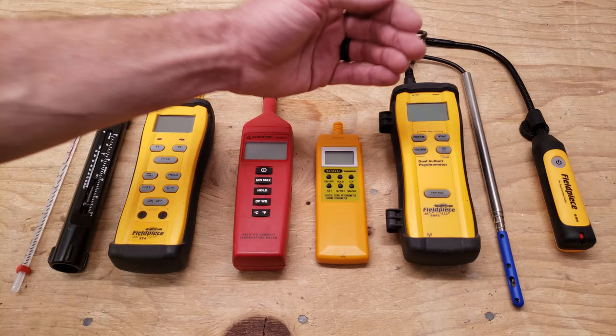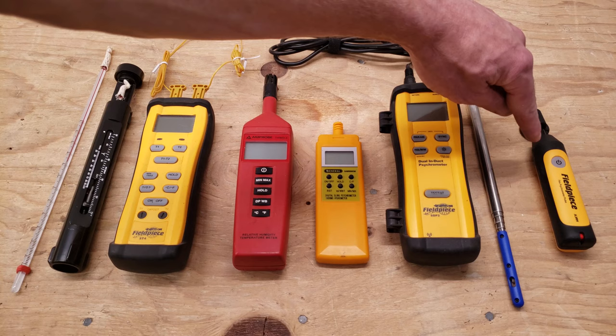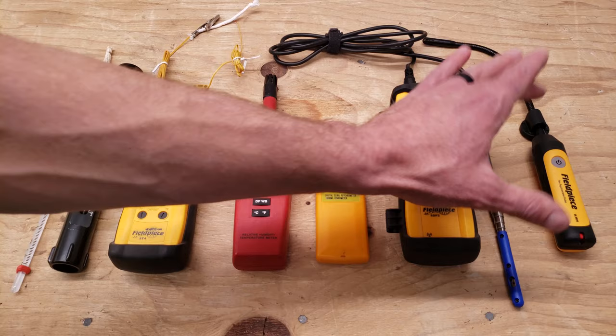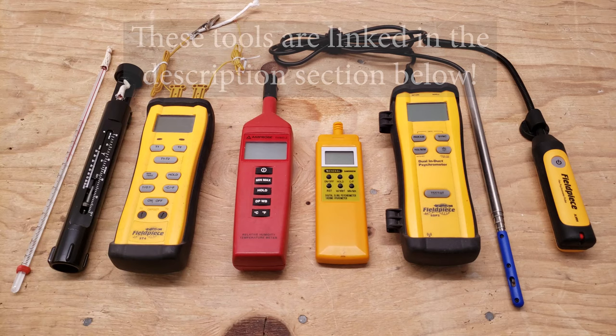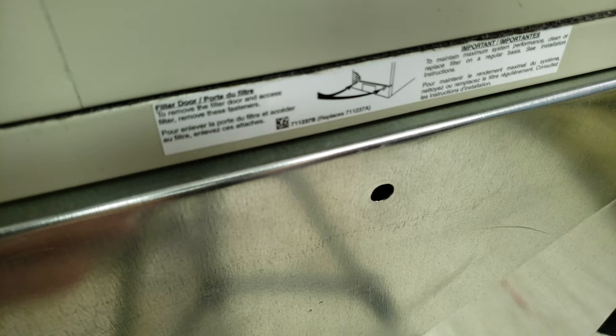But you got to remember as the system runs, your wet bulbs are going to lower, and that's going to make your target superheat change. This right here is a wireless probe, and through an app you can measure your indoor wet bulb temperature in real time. You can use the Fieldpiece Job Link app or another app for that. All these tools are linked down in the description section below, and I'm going to show you how each of these tools work.